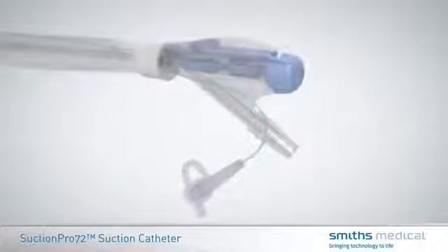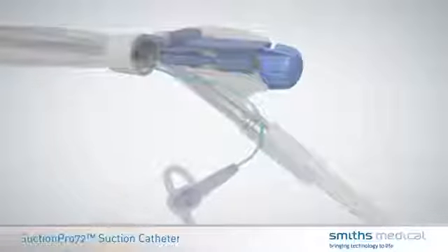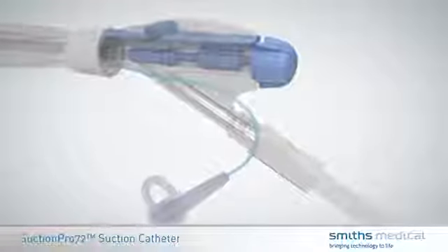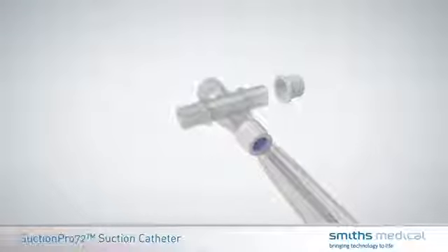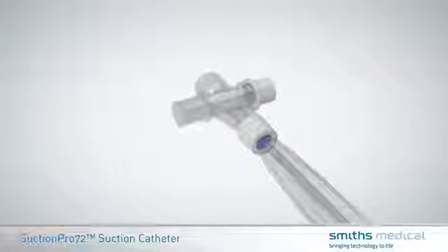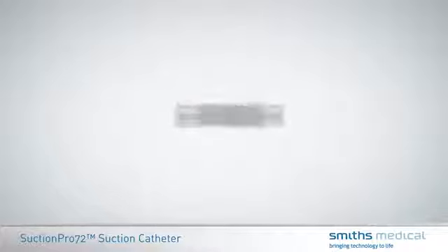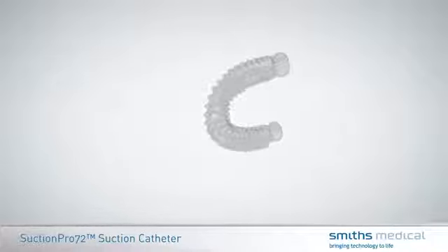Attach the suction tubing to the male connector of the SuctionPro 72 thumb valve. Place the cap on the side port of the T-piece which is not being used. An expandable flex tube is available for easy connection. This tube provides clinicians with the mobility to bend and shape the tube to the needs of their patient and reduces torque on the patient's airway.